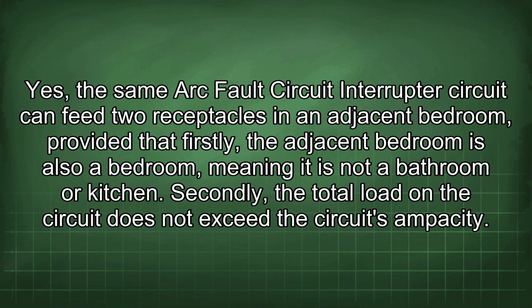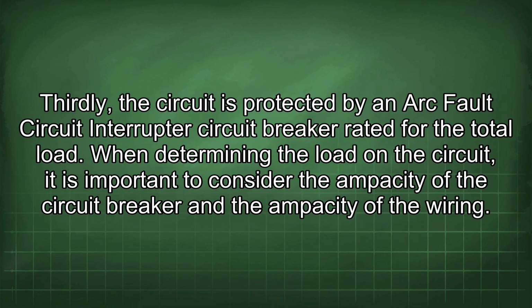Yes, the same arc fault circuit interrupter circuit can feed two receptacles in an adjacent bedroom, provided that, firstly, the adjacent bedroom is also a bedroom, meaning it is not a bathroom or kitchen. Secondly, the total load in the circuit does not exceed the circuit's ampacity. Thirdly, the circuit is protected by an arc fault circuit interrupter circuit breaker rated for the total load.